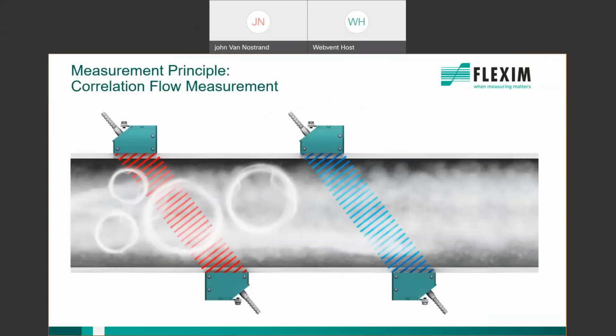FLEXIM can even measure steam in low pressure and high pressure applications. For low pressure applications, we use the transit time method, as I just explained. For high pressure steam applications, we use a method called the correlation method, or CFM for short. I'm not going to talk about it too much because it's not that common in water and wastewater applications, but it's worth mentioning because FLEXIM is the only company that can do this: high pressure, high temperature steam.